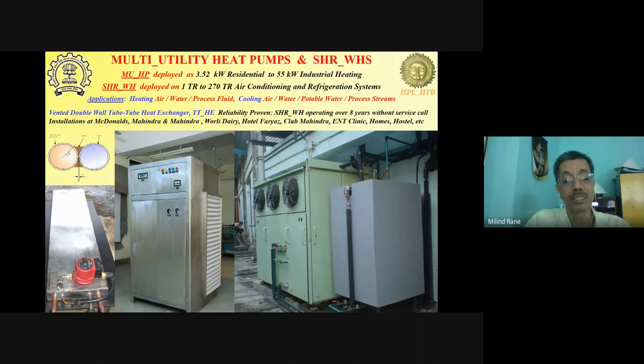Okay, and this particular unit with a footprint of only 1 meter by 1 meter is capable of generating around 36 kilowatts of heating using a 8.3 ton nominal capacity compressor. Now, we have also deployed similar size units with a 12-ton compressor, where the heat exchangers on the evaporator side would be extended all the way to the top, and the filters will also be extended to the top, and then we could give up to 55 kilowatts of hot water or heating duty from that particular unit, while concurrently giving around 42 kilowatts of air conditioning plus chilled water as and when required.